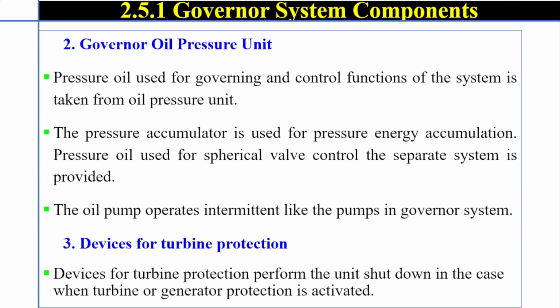The second one is the governor oil pressure unit. Pressure oil used for governing and the control functions of the system is taken from the oil pressure unit. The pressure accumulator is used for pressure energy accumulation. Pressure oil used for spherical valve control: a separate system is provided. The oil pump operates intermittently like the pumps in the governor system. The third one is devices for turbine protection. Devices for turbine protection perform the unit shutdown in the case when turbine or generator protection is activated.